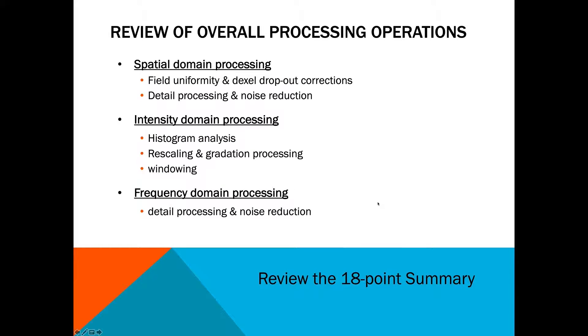To review the overall processing operations: spatial domain processing covers field uniformity, dead pixel dropout corrections, detail processing, and noise reduction. Intensity domain processing covers histogram analysis, rescaling, gradation processing, and windowing. Frequency domain processing covers detail processing — which is edge enhancement — and noise reduction. I would highly recommend reviewing the 18-point summary at the end of the chapter, as it does a fantastic job summarizing everything.